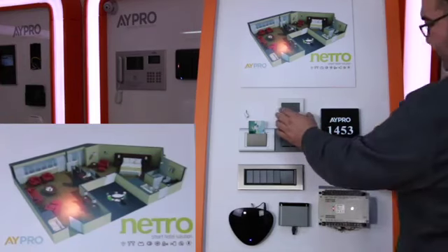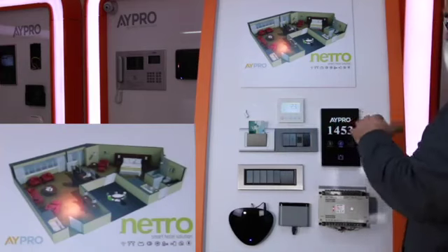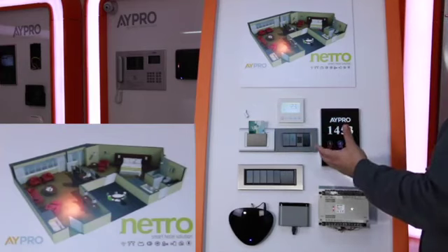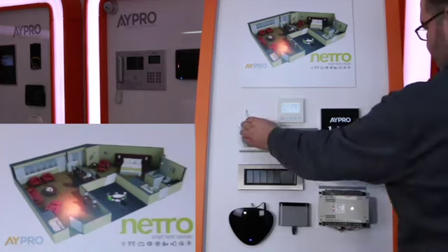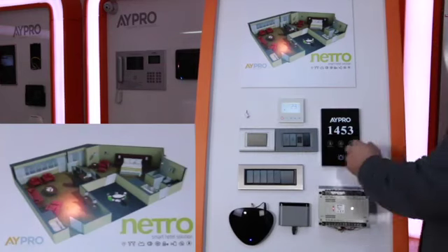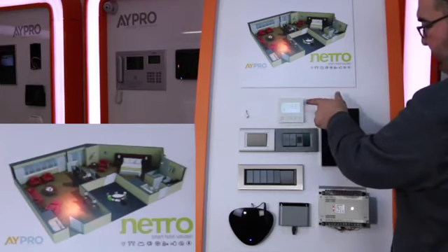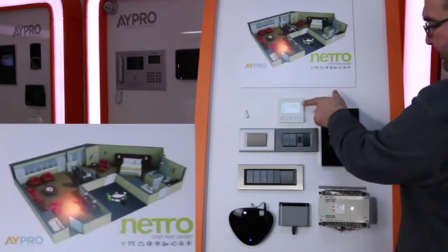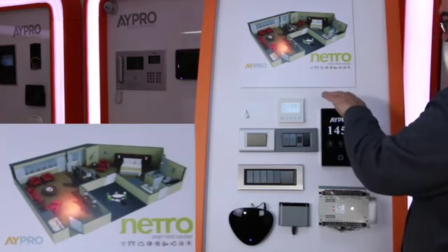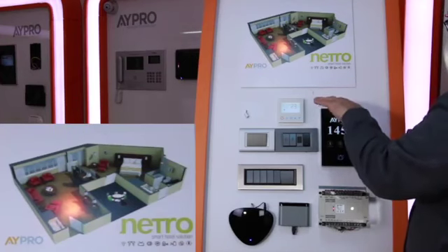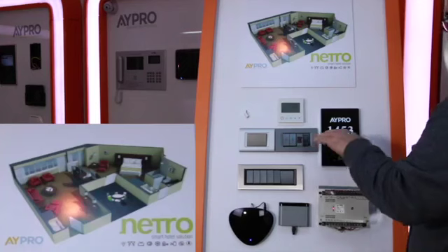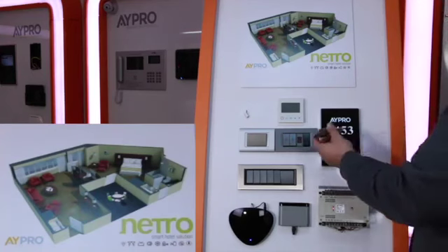And also, this thermostat and the total system have some energy saving modes. Besides, this card can work like an energy saver. This thermostat also has a sleep mode. When you press the sleep mode, in 1 hour the set temperature goes 1 degree down, and in the second hour 1 more degree down. So in total, you have 2 degrees of energy saving.